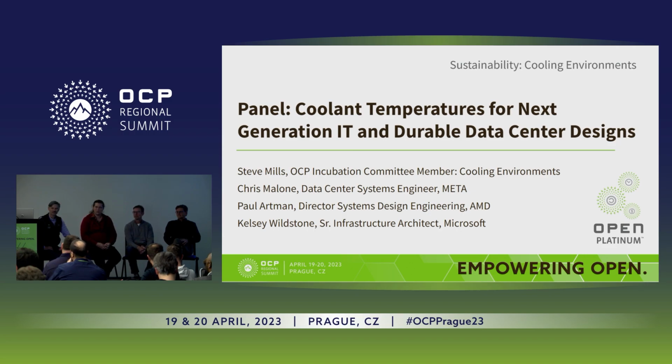Right, so now we're finally bridging the gap from the FWS to the silicon, and so we can say, okay, we've designed a facility where the FWS is maybe designed for W27, the TCS is designed for an S30, and then as long as the owner brings in and installs S30 class servers or higher, then they're good. Exactly.